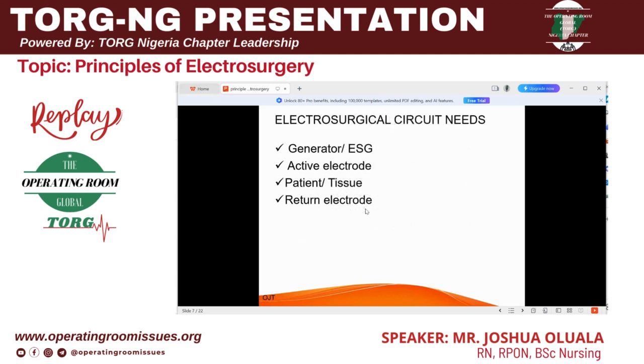in place. Then, when we are talking about the electrosurgical unit, what are those things that we put together to actually call it an electrosurgical unit? So the electrosurgical circuit needs the generator, or electrosurgical generator. Then the active electrode must also be available. And the patient or tissue, of course; the tissue you are going to use it on must also be available. Then the return electrode, in the case of monopolar, the return electrode that will take electric current from the body of the patient back to the generator.